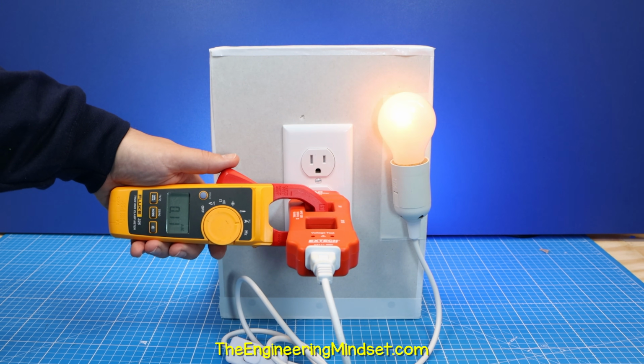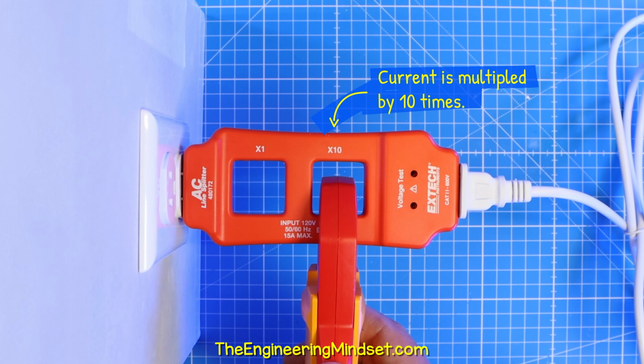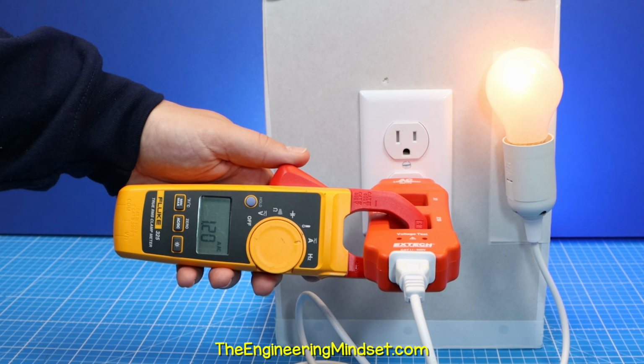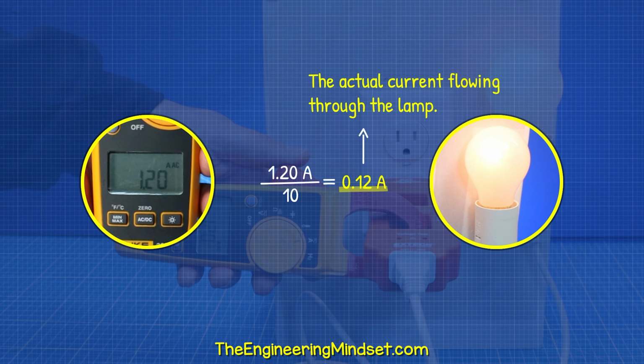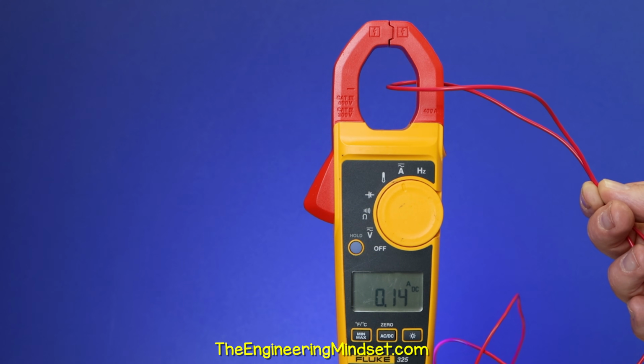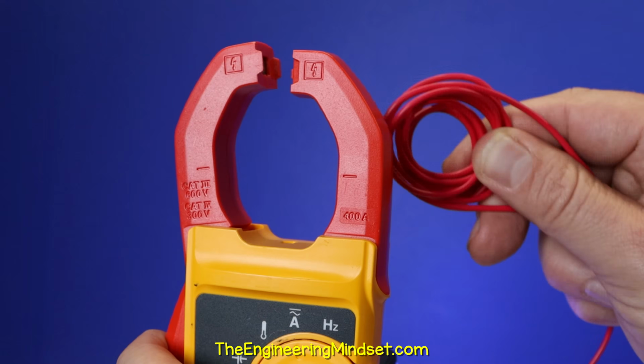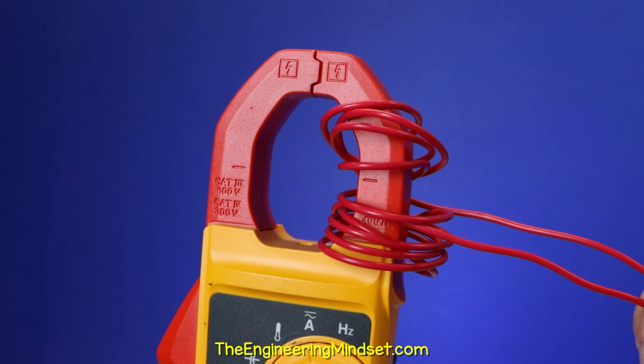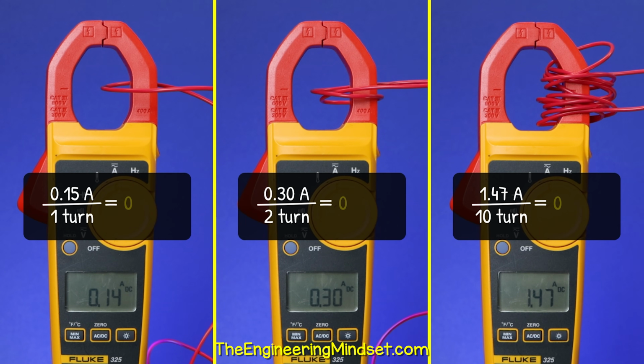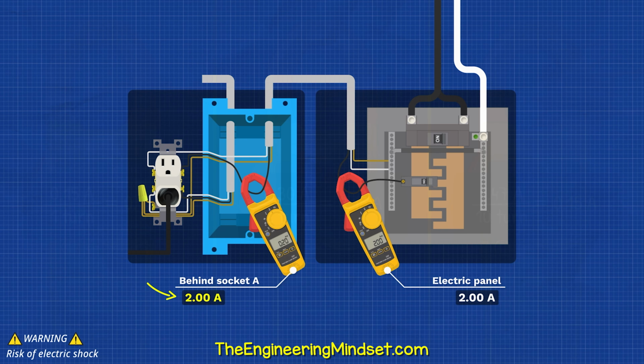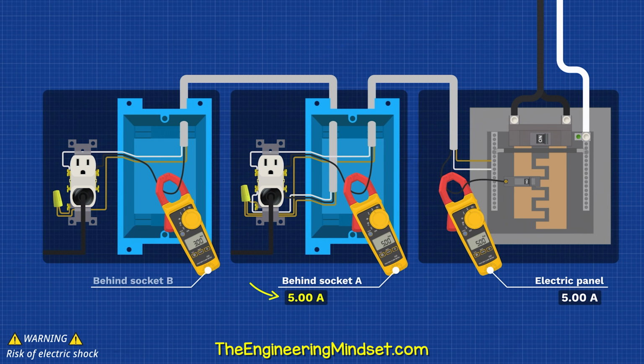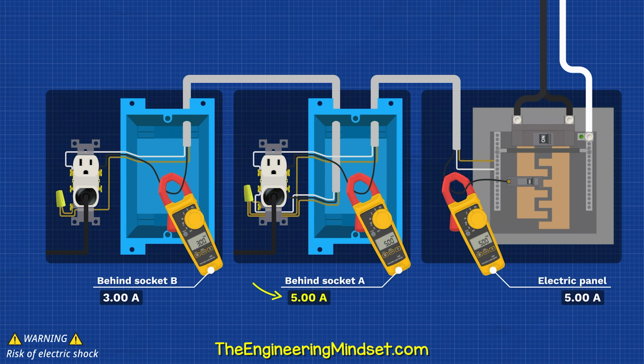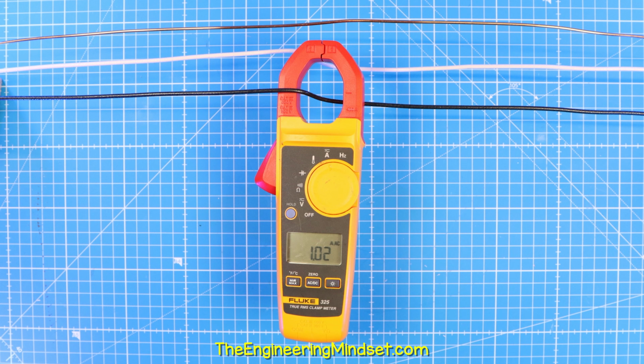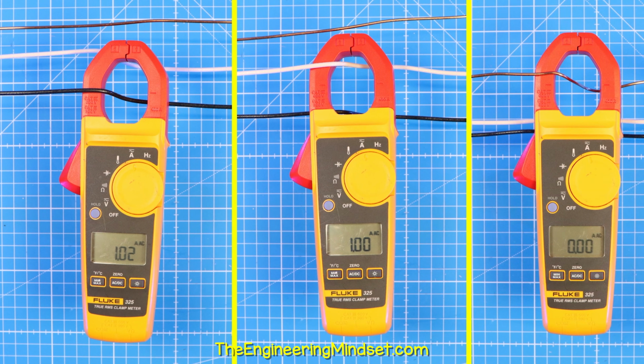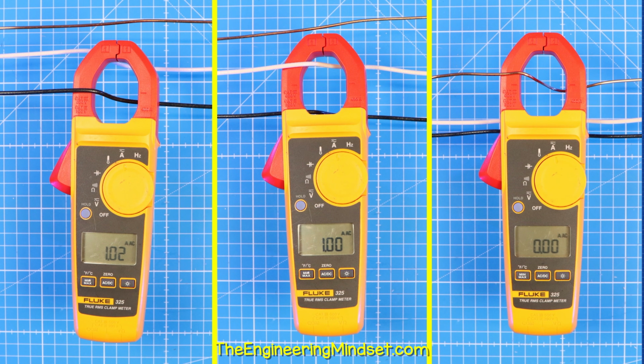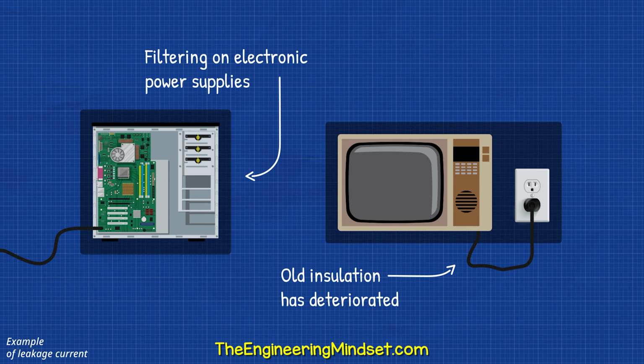If the current is very small, we can use the 10x section, which will simply multiply the value by 10. So we must therefore divide this value by 10. Alternatively, for small currents, we can wrap the wire around the clamp to increase the current reading. But we have to divide this by the number of turns. You can take measurements behind sockets, but do consider what else is connected to that wire. The current should be roughly the same on both the hot and the neutral, with ideally 0 amps on the ground, although some devices will have a leakage current.